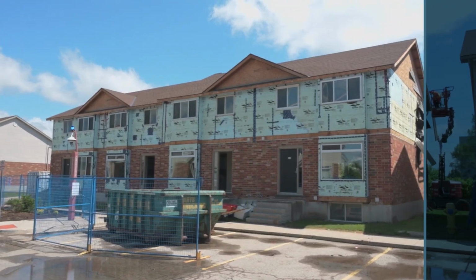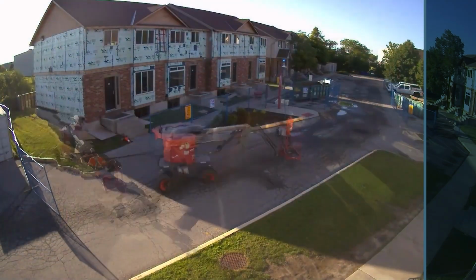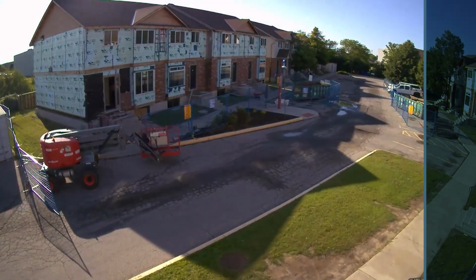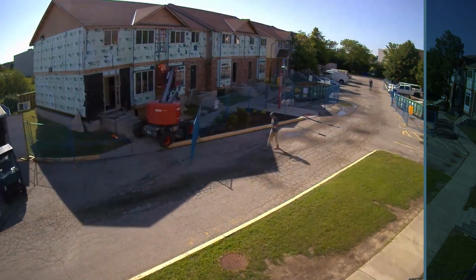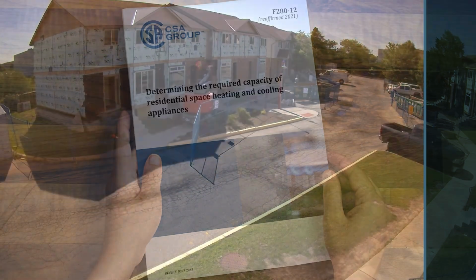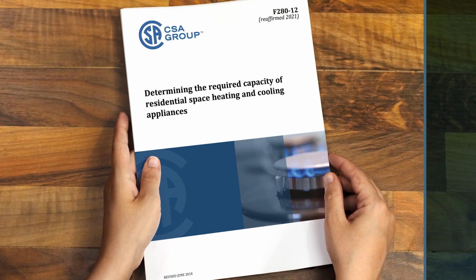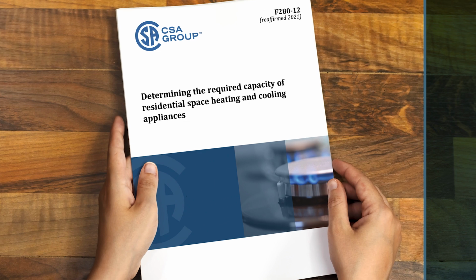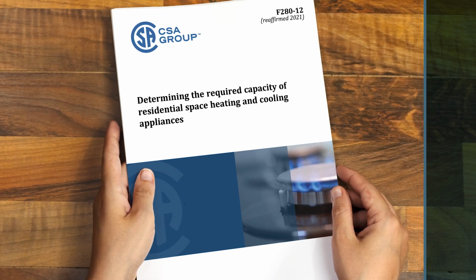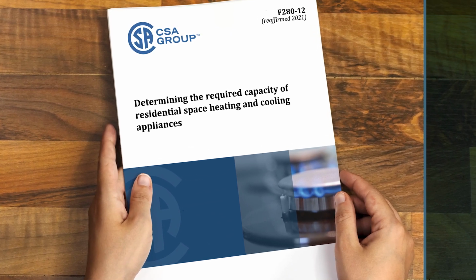We asked ourselves, what energy efficiency improvements do we need to make to hit this target? Here, we wanted to go net zero. For new construction and renovations, there's now a trend towards right-sizing based on proper heat loss and heat gain calculations. The methodology is laid out in CSA standard F280-12 and baked into many calculation software packages. It allows us to more accurately predict the building's heating and cooling requirements.